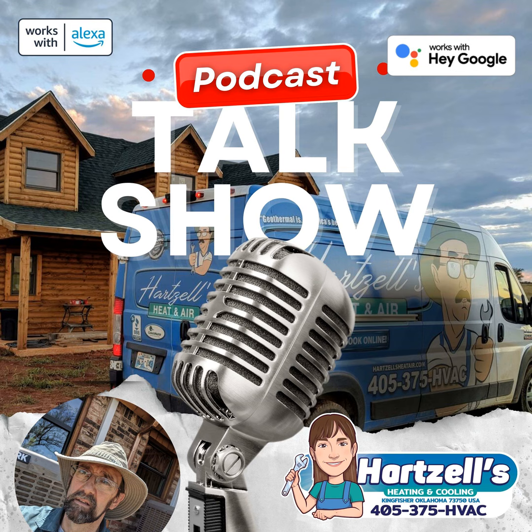It's like trying to move a sofa. If it's just a small love seat, you can probably move it even if you pulled a muscle in your back. But if someone asks you to move a grand piano, you physically just can't do it. When the afternoon sun is beating down on your roof and it hits 95 or 100 degrees outside, your house reaches its peak heat load. The system needs 100% of its lifting capacity to move that much heat from inside to outside. If it is missing refrigerant, it lacks the physical mass to keep up.